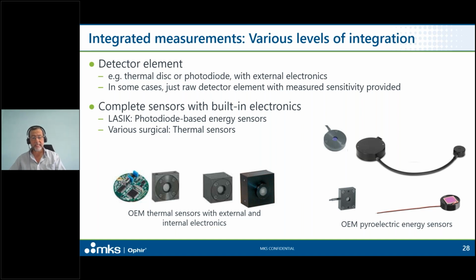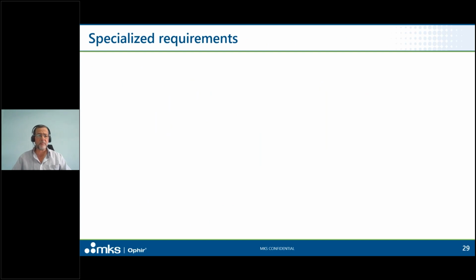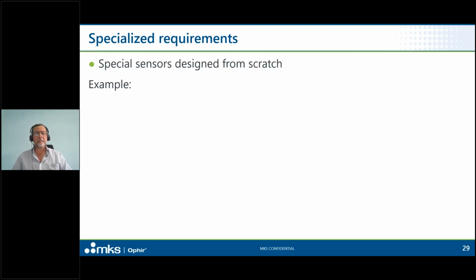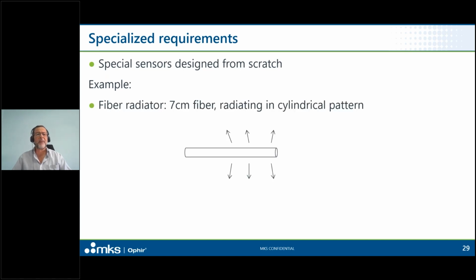Sometimes there are special requirements that really need something that's going to be designed from the ground up. So I just want to show you one example of that. This is actually one of my favorite solutions that we've done at Ophir. Medical customer, medical device manufacturer. And for this particular application, their light source is a fiber emitter, except this fiber emitter doesn't emit the beam out of the tip of the fiber the way we usually think of fiber emitters. Rather, the last 5, 6, 7 centimeters of the length of this fiber are rough polished, and the light is emitted in a cylindrical pattern from the last 5, 6, or 7, whatever centimeter length of this fiber. And the customer obviously wants to measure the total power being emitted from here before they start using this inside the body of a patient.